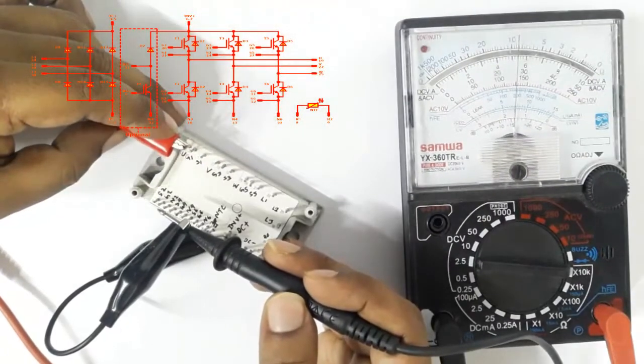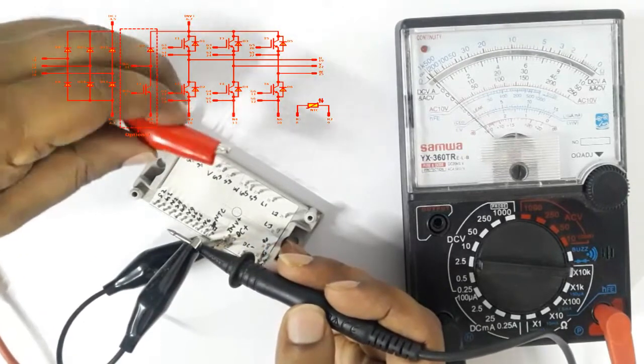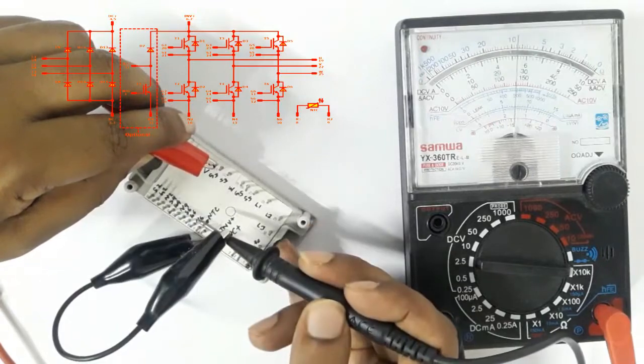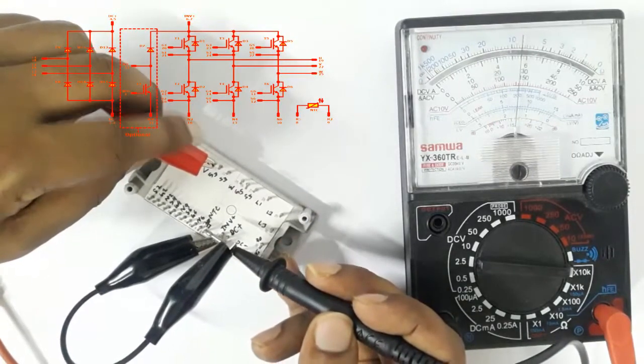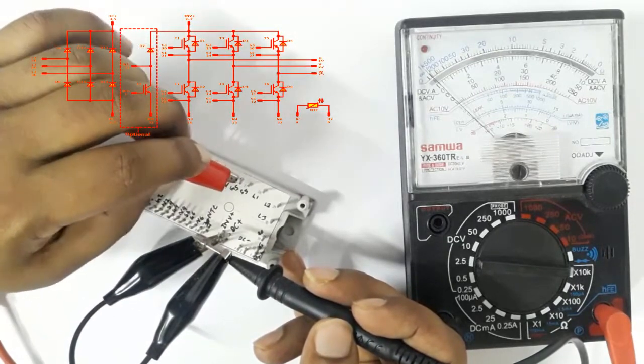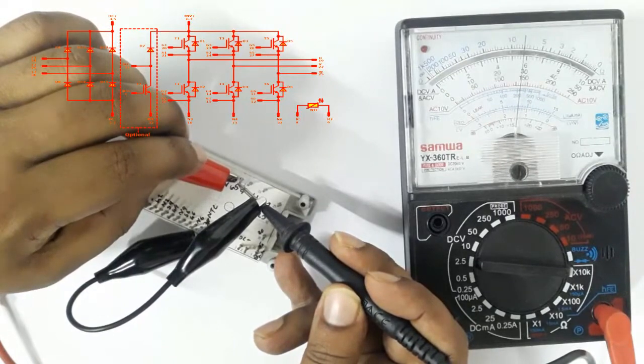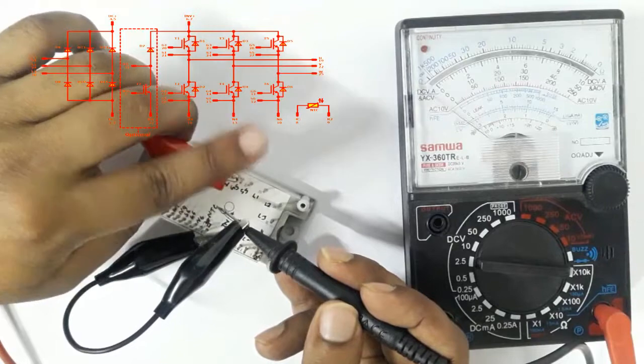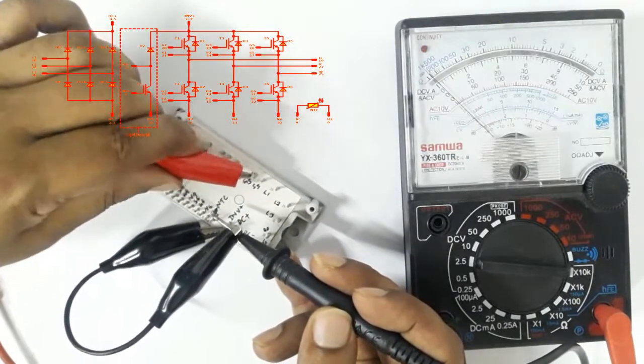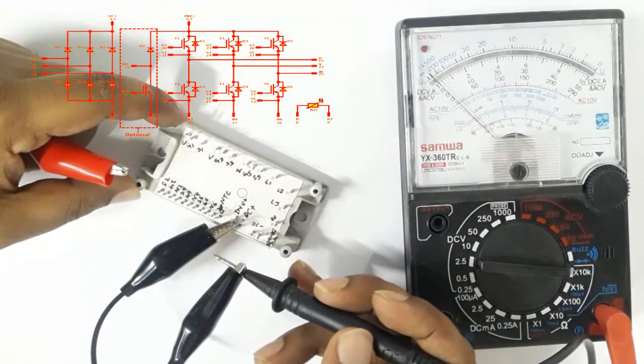It's working and it's off. Now testing gate for V, it's working. Now testing for W. First negative terminal, then gate. All are working. Here we're testing three gates. Now we need to test three more gates because one IGBT has six gates.